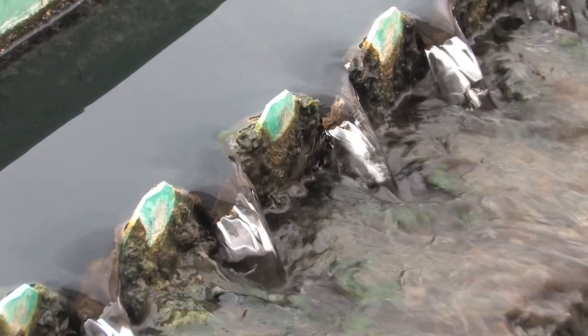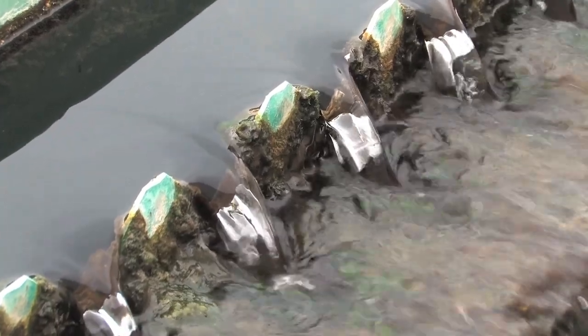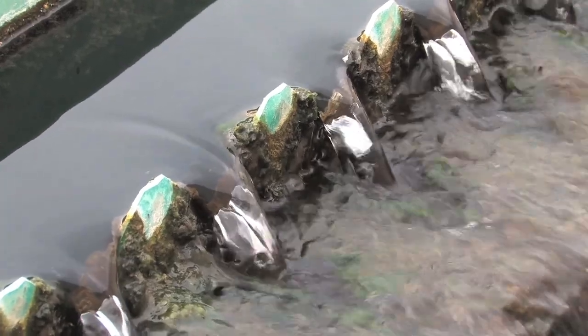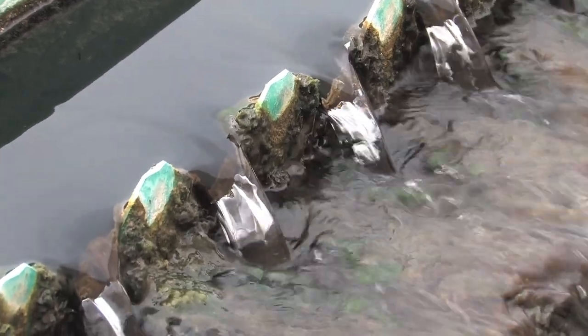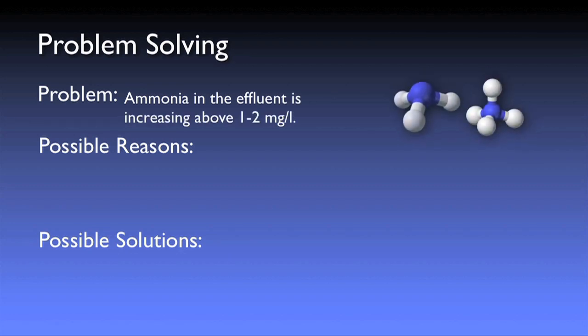Various levels of denitrification may be required depending on the local discharge permit. However, full biological denitrification typically results in only 1–3 mg of nitrate in the effluent stream. Now let's take a look at some real-life operational scenarios. During your routine operational sampling, you notice that the ammonia in the effluent is beginning to rise above 1–2 mg per liter. Let's think about what could be causing this.